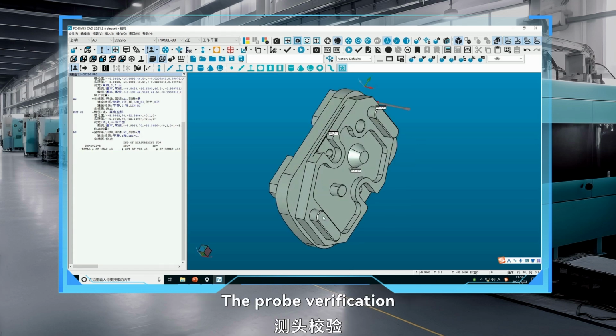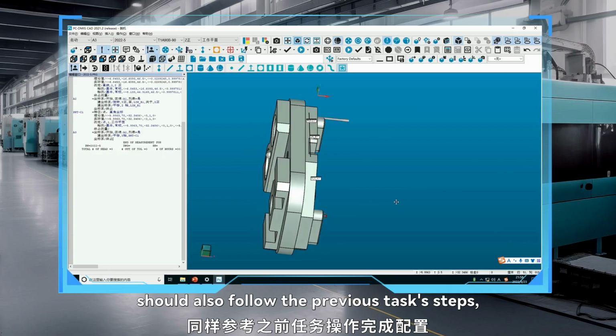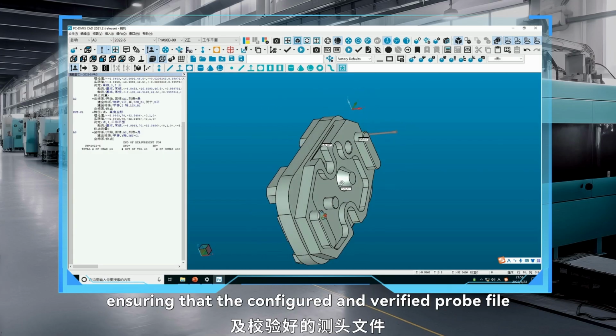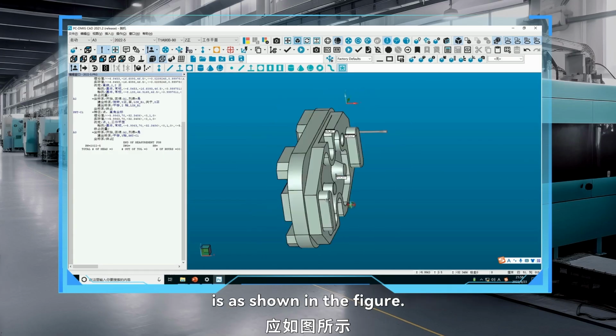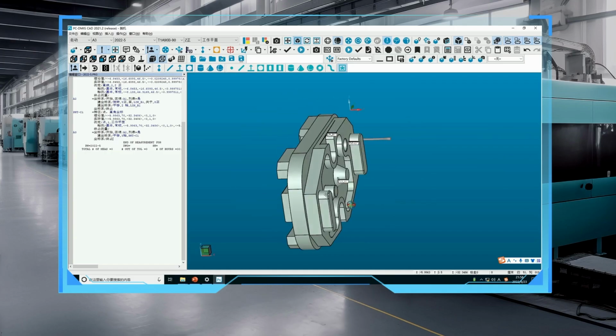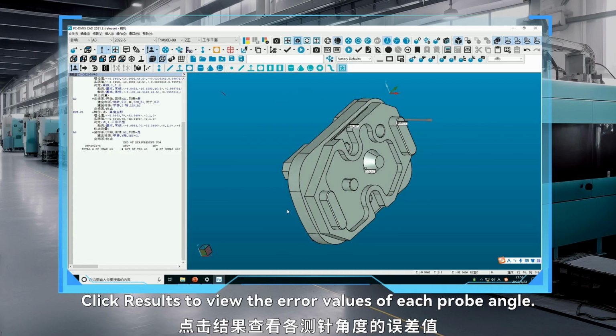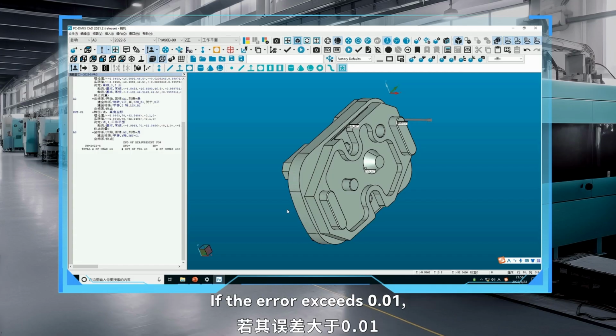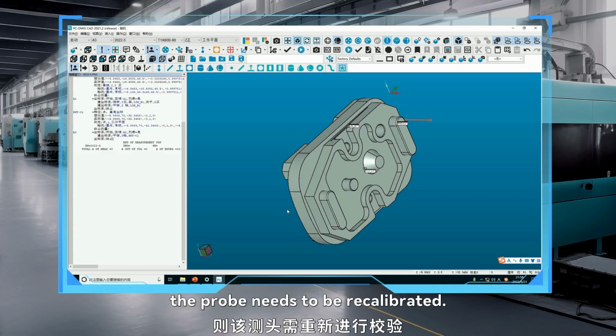The probe verification should also follow the previous task steps, ensuring that the configured and verified probe file is as shown in the figure. Click Results to view the error values of each probe angle. If the error exceeds 0.01, the probe needs to be recalibrated.